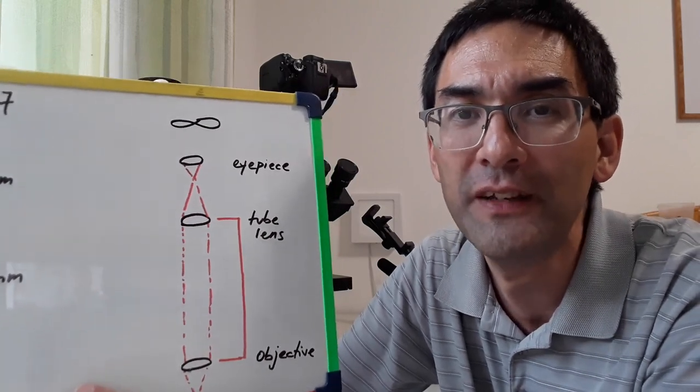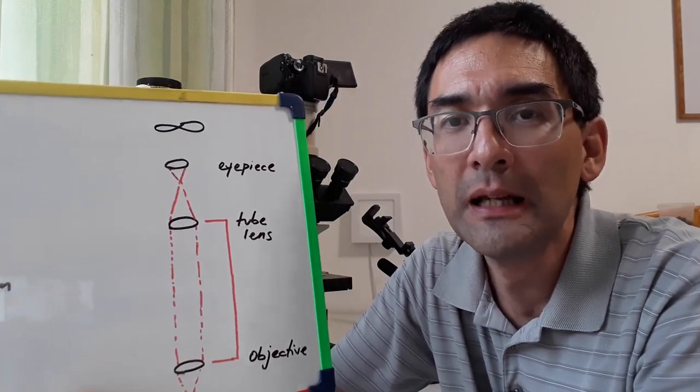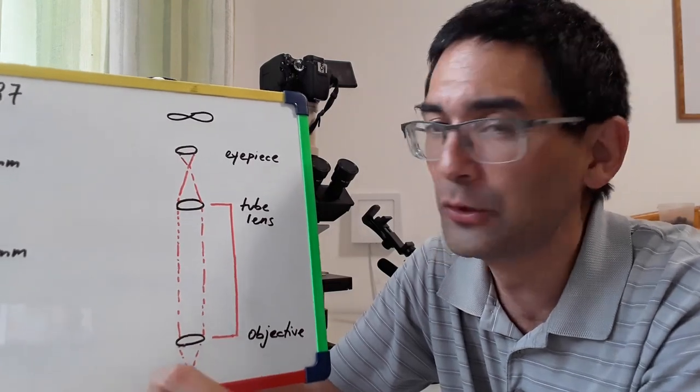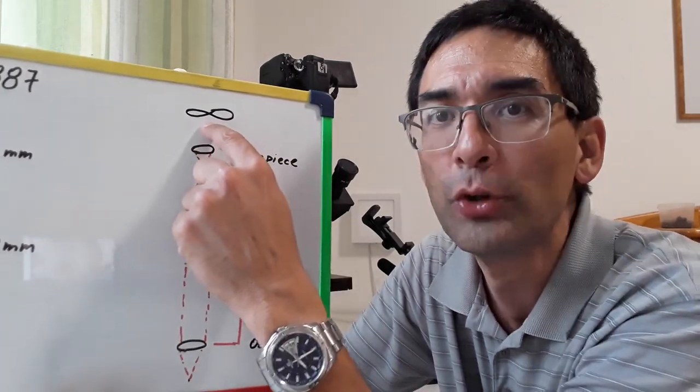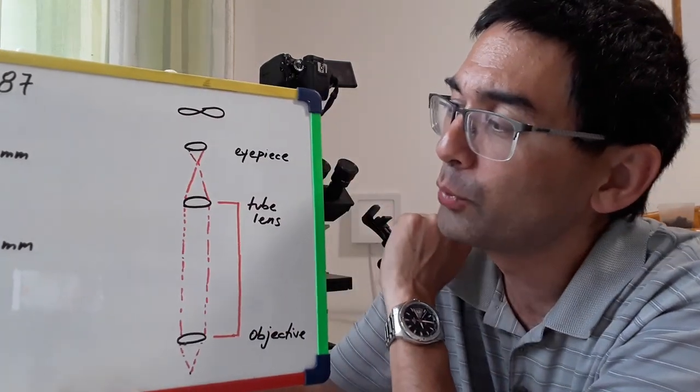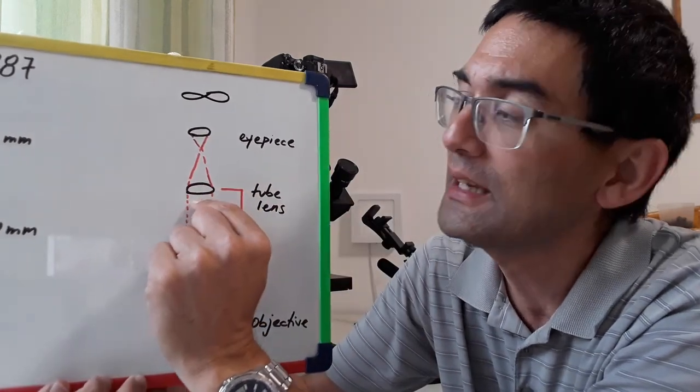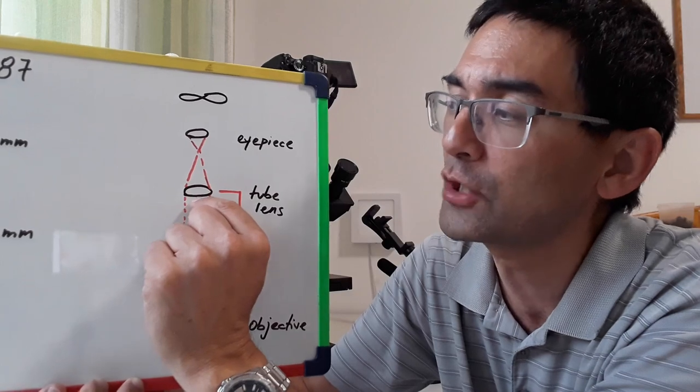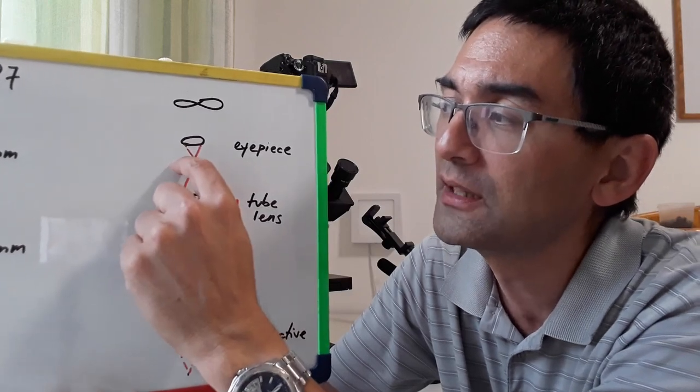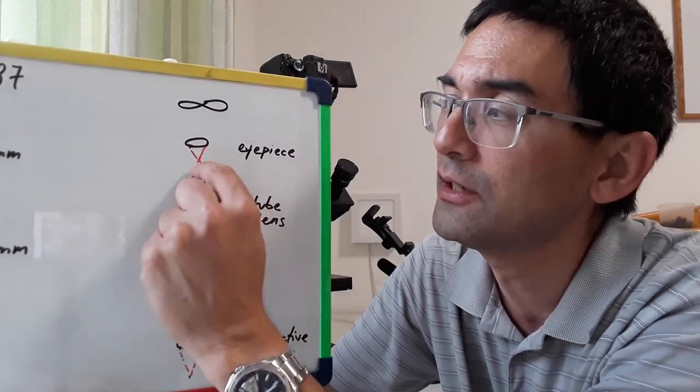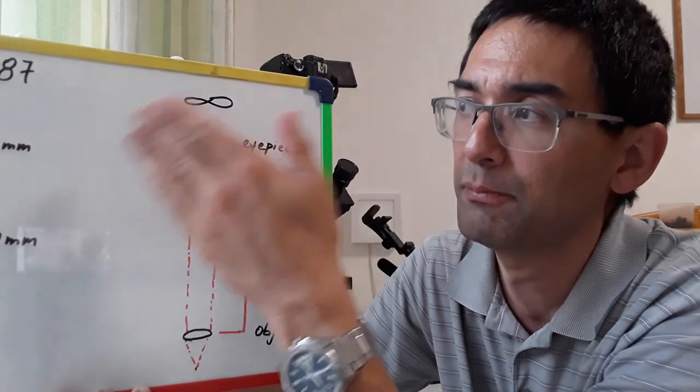And because this one here, the objective, now focuses the light into infinity, infinitely far away because the light beams are parallel, therefore you refer to these objectives as infinity. Now unfortunately I don't have an infinity objective with me right now so I cannot show you how it looks like but there is this infinity sign printed on the objective. But what you need now is a so-called tube lens and this tube lens is now inside the microscope tube.